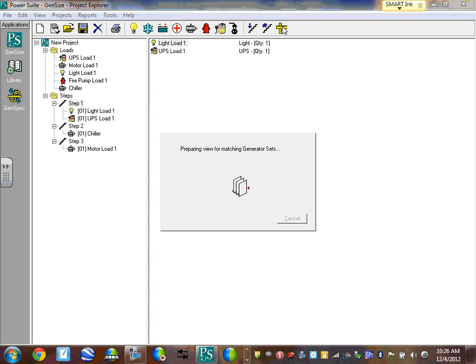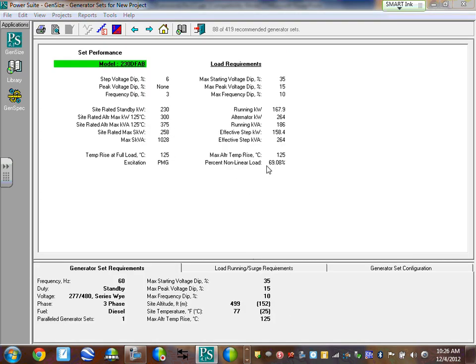Percent nonlinear. Does it have a total percentage load? Load running, the second tab, I think it gives you load running and surge requirement. Hmm? I'm looking at the one. You want a total running KW? No, I'm looking at the amount of load versus the size of the set. Okay, alternator KW is 264. Alternator max is 300. Okay, so that's starting size. Running KW is 167.